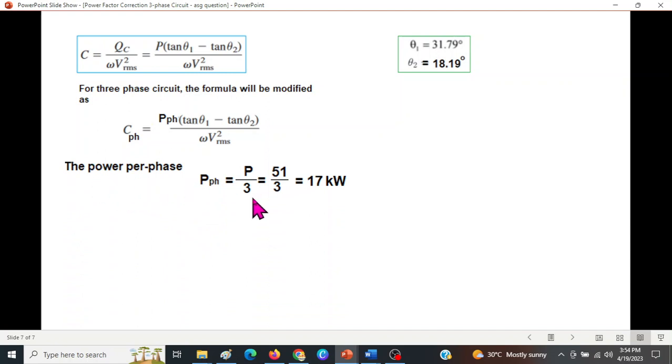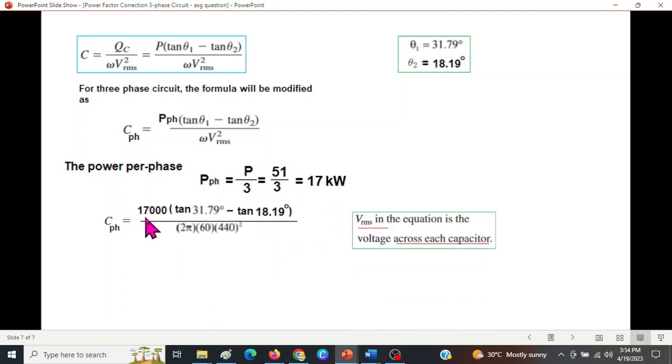And the power per phase is the total power which was 51 kilowatt divided by 3, so 17 kilowatt. We will put this value here: 17 kilowatt, then the tan θ₁, tan θ₂, 2π × 60, and Vrms as I mentioned here, it is the voltage across the capacitor which is given in this question, 440 volts. So we will use that. And solving, we find the answer to be 67.82 microfarad. So I hope you have been able to follow this. Please let me know through your feedback. Thank you.